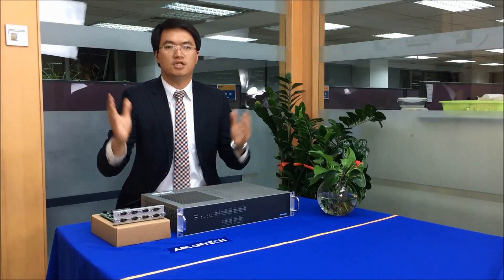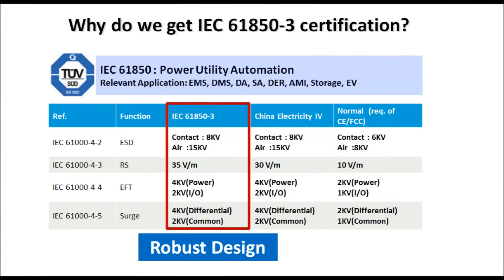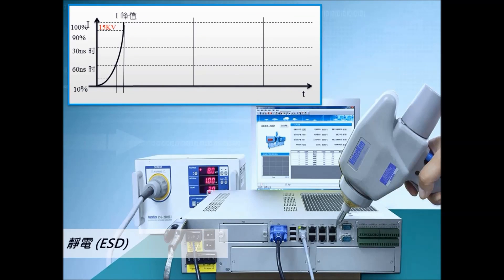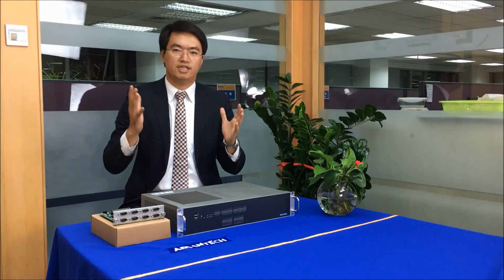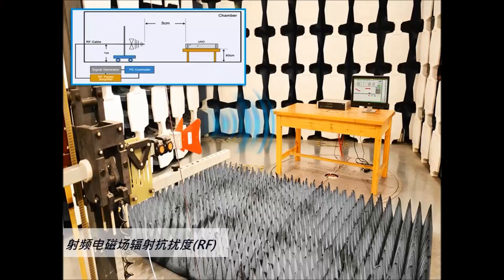The ECU 4000 has been certified to IEC 61850-3 for electromagnetic protection in high-voltage environments, which is typically twice as strict as that required for a normal industrial PC. For example, there's a 15kV electrostatic discharge test compared with a normal 8kV, and in radio frequency testing, ECU products are tested to 35V per meter, compared to the more usual 10.